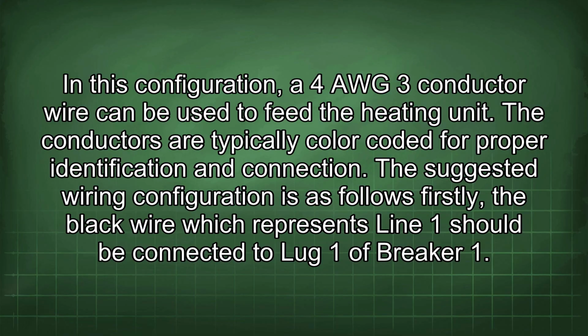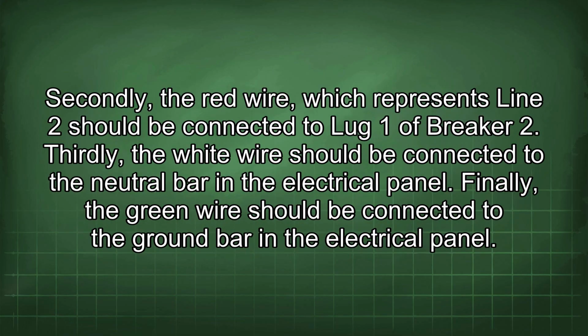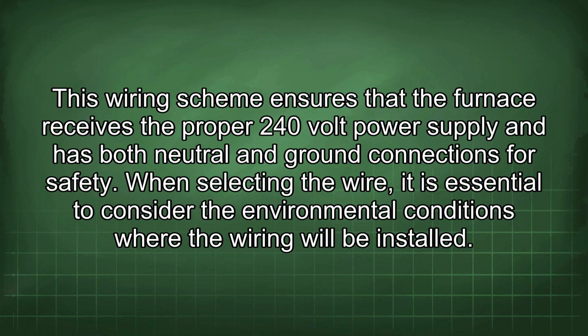The conductors are typically color-coded for proper identification and connection. The suggested wiring configuration is as follows. Firstly, the black wire, which represents line 1, should be connected to lug 1 of breaker 1. Secondly, the red wire, which represents line 2, should be connected to lug 1 of breaker 2. Thirdly, the white wire should be connected to the neutral bar in the electrical panel. Finally, the green wire should be connected to the ground bar in the electrical panel. This wiring scheme ensures that the furnace receives a proper 240-volt power supply and has both neutral and ground connections for safety.